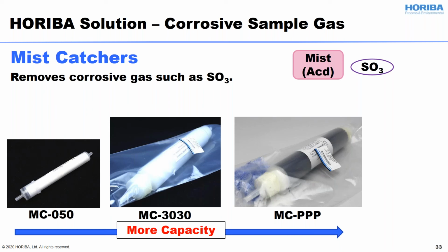HORIBA provides the mist catcher to capture the SO3. This is the SO3 mist catcher, and there are a couple of models, depending on the concentration of SO3. If you have more capacity, you're going to need a bigger mist catcher. SO3 is extremely corrosive, and once it comes into the analyzer cell it gets rust. So the analyzer will be very difficult to keep its performance in this case. So HORIBA provides this mist catcher as standard configuration.